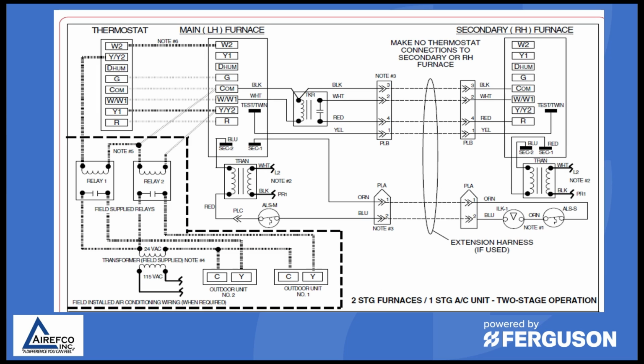A lot of twinning kits will use relays to transfer the signal from the thermostat to the furnaces and to accomplish other things such as heat pump applications. Many twinning kits will specify they're for air conditioners only, so if you're installing heat pumps, you'll want to make sure you get a twinning kit that will apply to heat pumps.